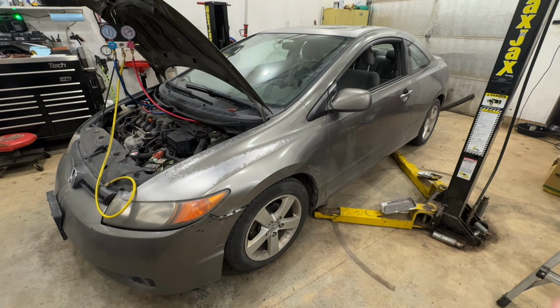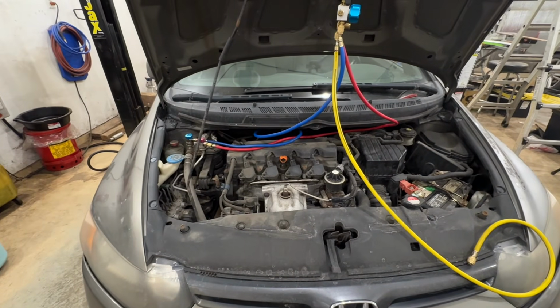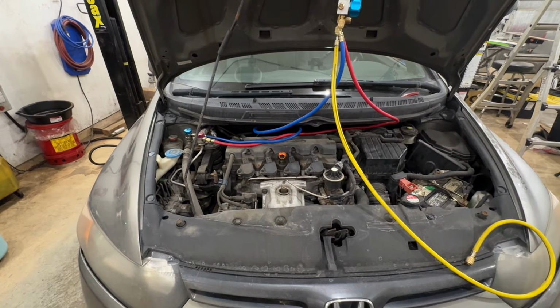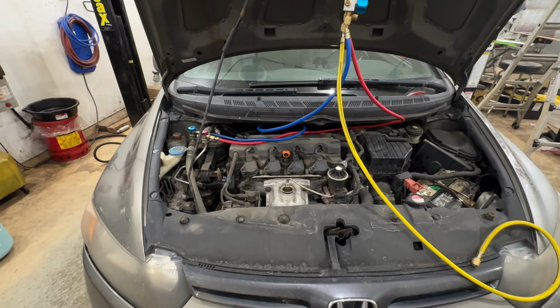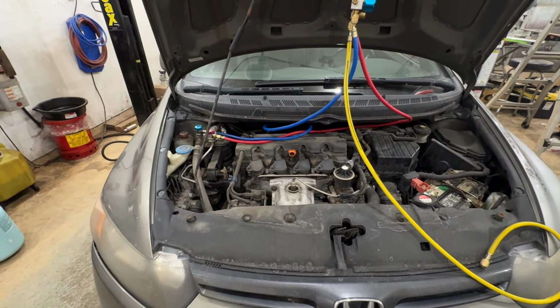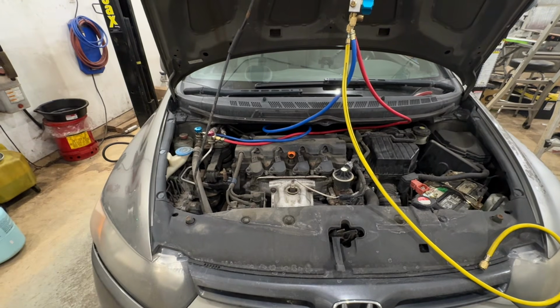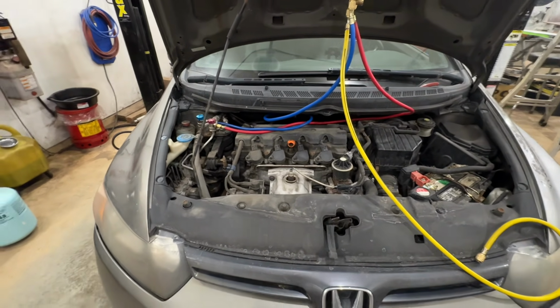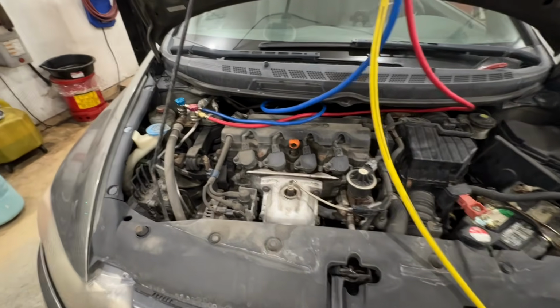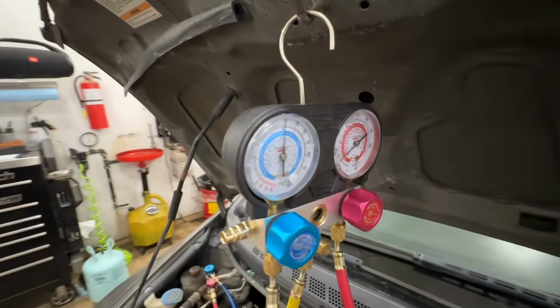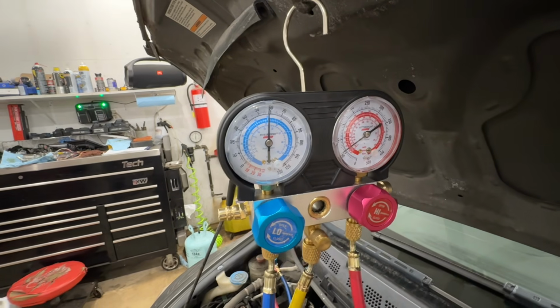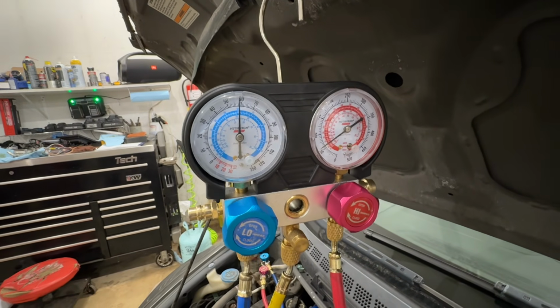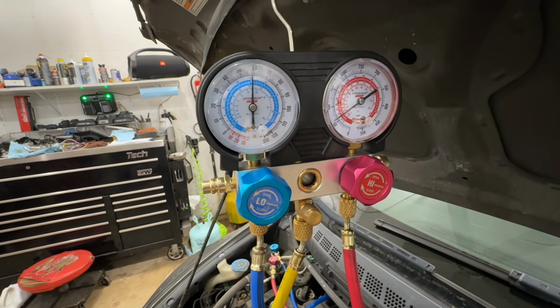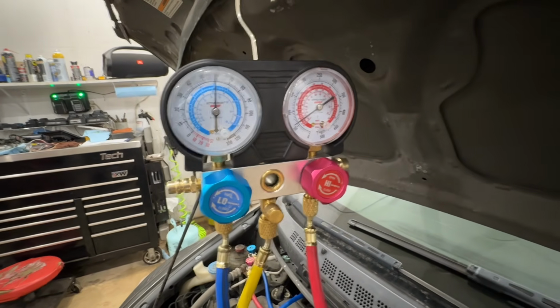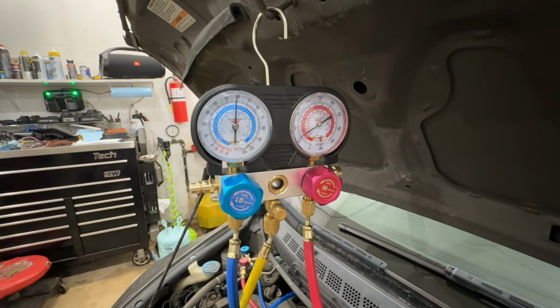So let's get started. The first thing I wanted to do was confirm there was refrigerant in the system. If the system has been discharged due to a leak or a shortage of refrigerant, the compressor won't kick on, it won't cycle. So I hooked my manifold setup to the high and low side. It's actually reading a little higher than it was because I've had it working now, but as you can see, I have pressure. I was at about 50 PSI on both the high and low side, which makes sense if it's not running. So I confirmed there was pressure.